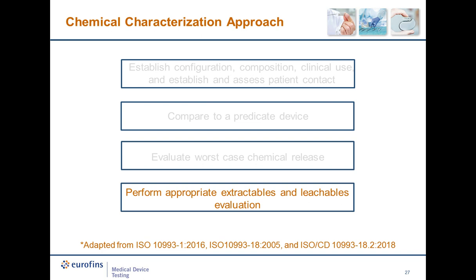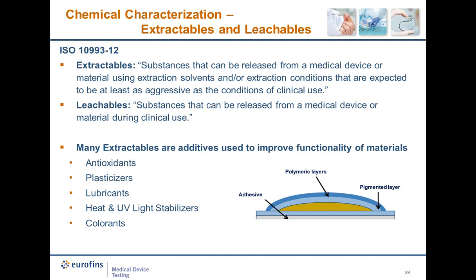However, if the sponsor is not able to establish that the entire composition of the device is acceptable to the patient, the sponsor should move to the next step of the process, which is an extractables and leachables evaluation. Before I describe how to design and perform an appropriate extractables and leachables study, I'd like to briefly touch on what extractables and leachables are and where they typically come from.